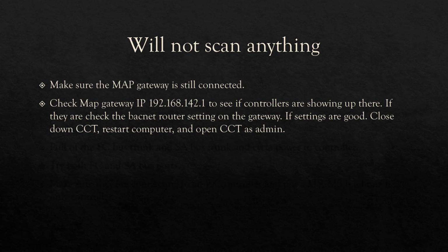Go to the GUI on the MAP gateway, go to the IP address, log in, and if you see controllers, then the Bacnet connection's good. Then it's a CCT problem to the MAP gateway. Close down CCT, and I would even restart your computer, then open up CCT as admin, log back in, and you're probably good.